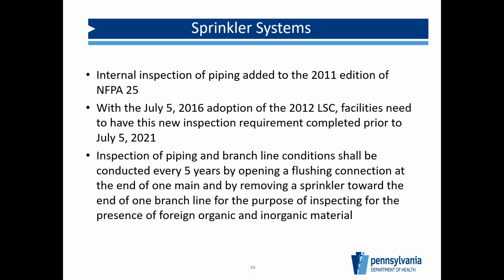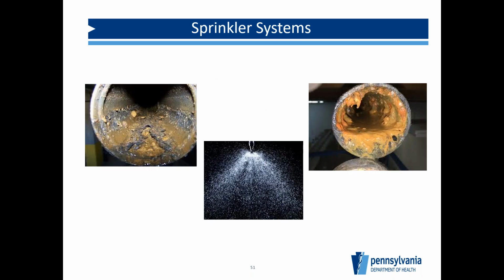And what they're looking for is foreign organic and inorganic material. We'll take a look at what that looks like, but I'm just trying to give everybody a heads up. So when we go out and do your survey this year, no, we're not going to ask for this. But come 2021, midway through the year, we're going to start looking for this. And if everybody is asking the sprinkler companies to do it at the last minute, they're not going to be able to provide that service, because it's a little more invasive than your normal survey, your normal testing and inspection by NFPA 25. So here's some pictures of inside. You can see they scraped some of the material out.